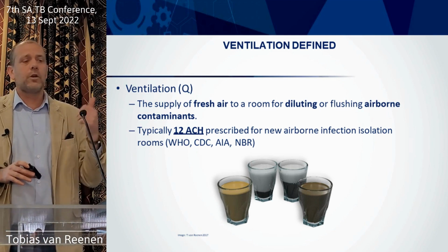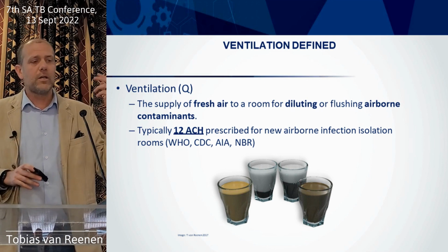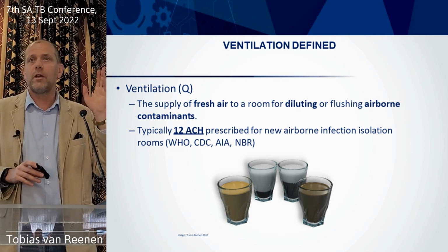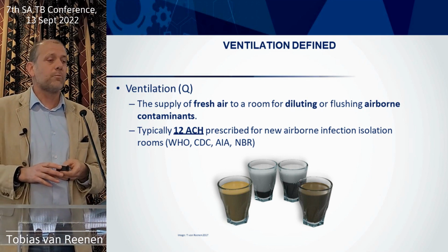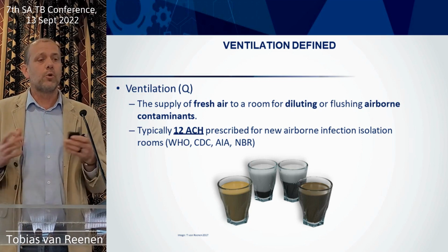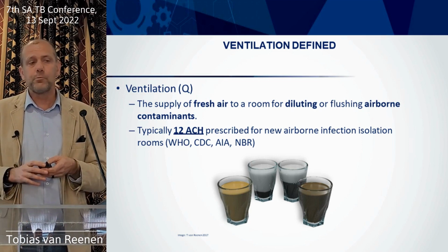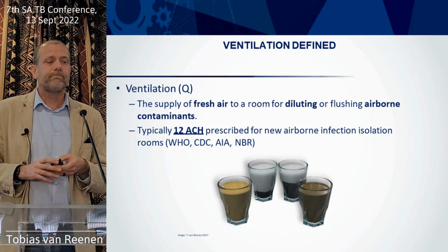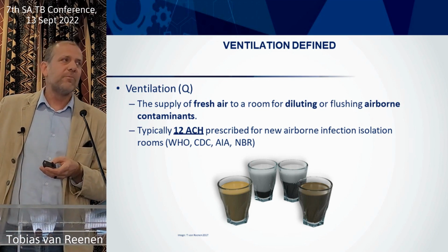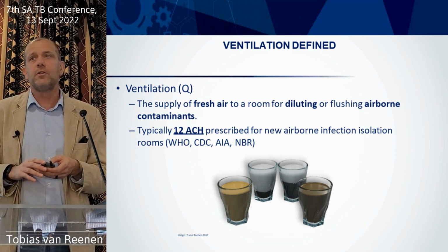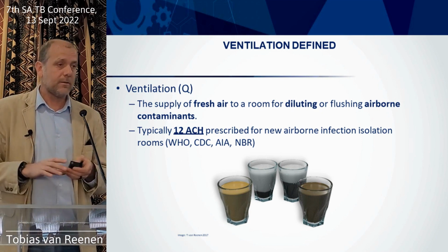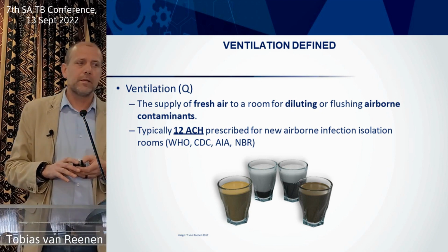Typically, the WHO, the CDC, the American Institute of Architects, our national building regulations, and many other sources prescribe 12 air changes per hour for airborne precaution rooms, or airborne isolation rooms. That's very often considered to be sufficient ventilation. I'd like to show you why that's problematic.